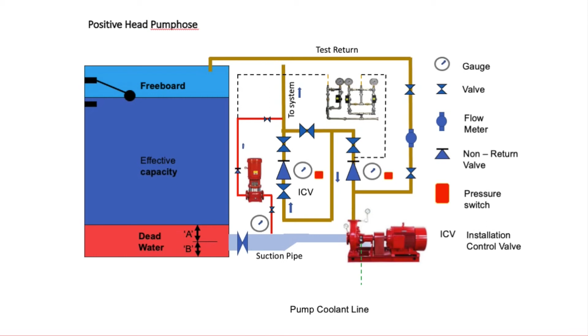And then at that point you've got a test return back into the tank so you can test the flow and pressure of each pump. Okay, so that's generally the schematic of how any sprinkler pump house operates. Now we talked about the ICVs. So what you tend to get in warehouses is ICVs such as this.